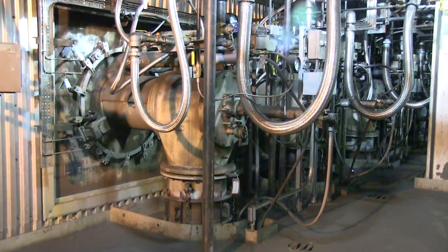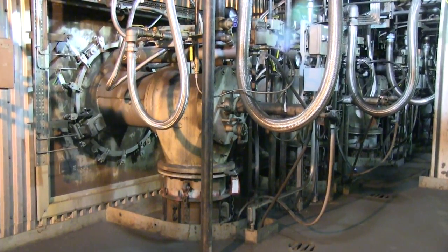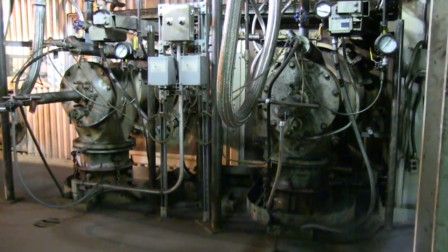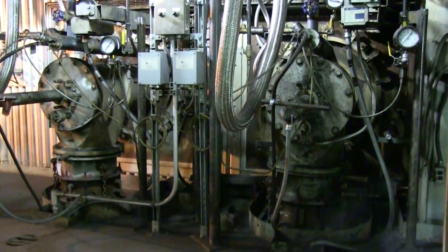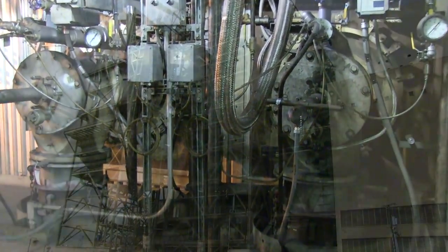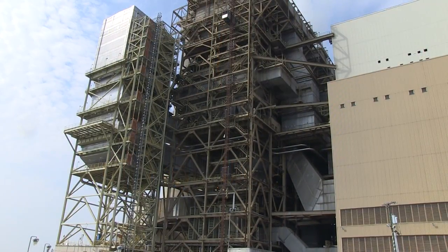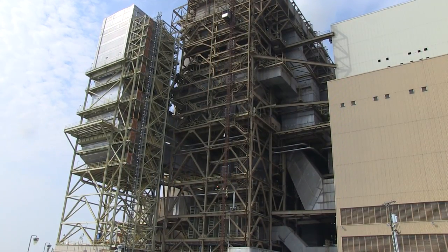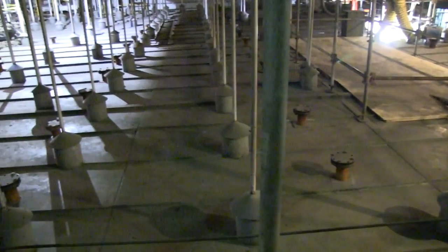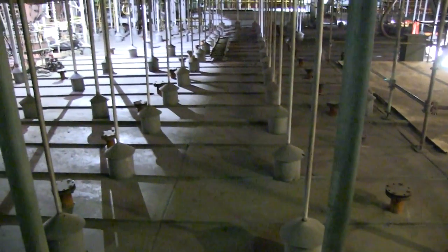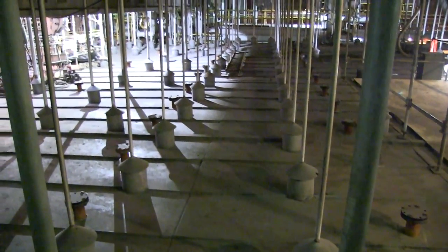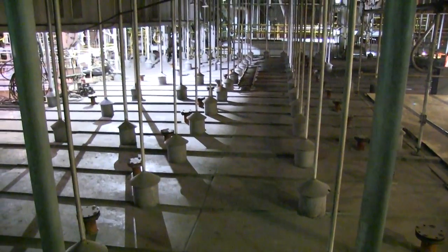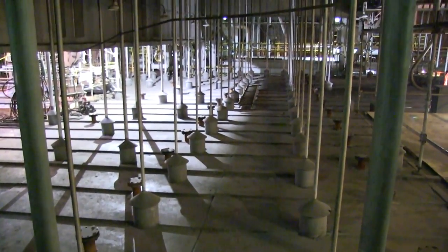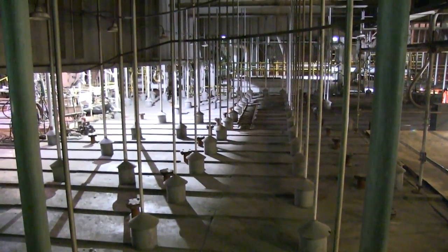observer to see. It's surrounded by the pipes that move air and coal in, fans that draw air in and out, tubes that move water around the boiler, pipes carrying steam to the turbine, and pollution control equipment. The boiler itself is suspended from the top of the building which houses it, because the temperatures inside can cause it to expand downward by as much as 12 to 18 inches.